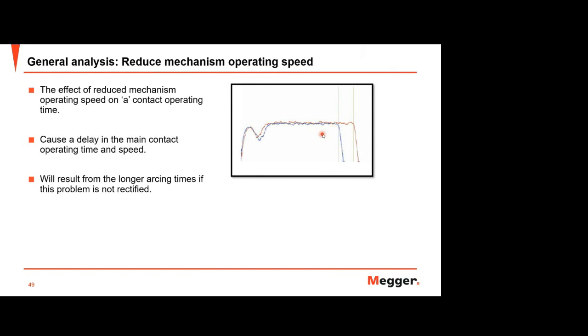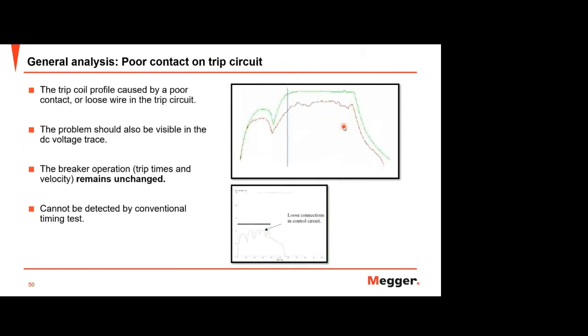Yeah, this one, increased contact erosion and insulator contamination will result from the longer arcing. So if you consider the arcing time, it will affect this issue. So you need to consider it, but mostly on the mechanical part. And you can see this one, poor contact on trip circuit. This is an example of this issue. The general form of the profile is valid for both. You can do it for trip or close coil.